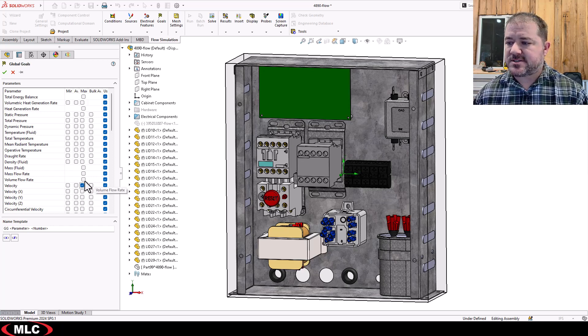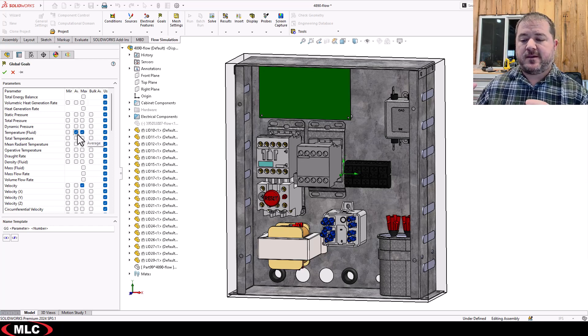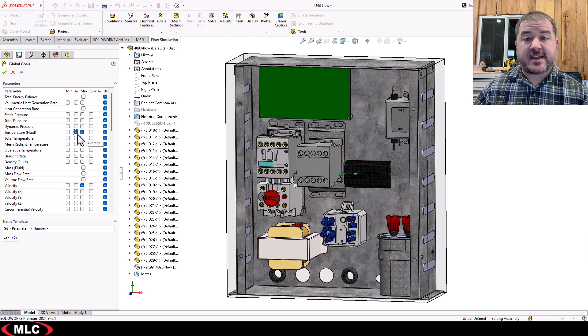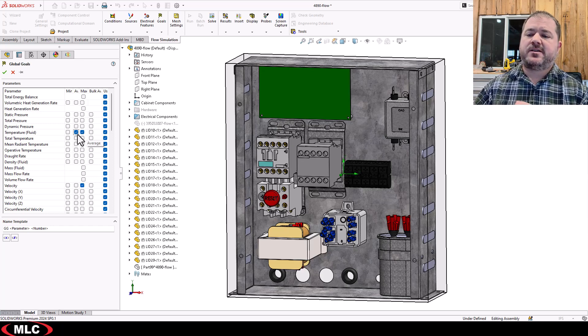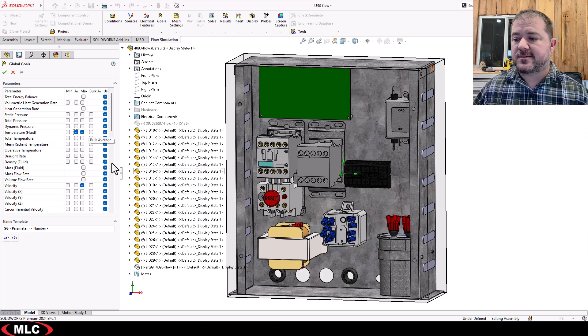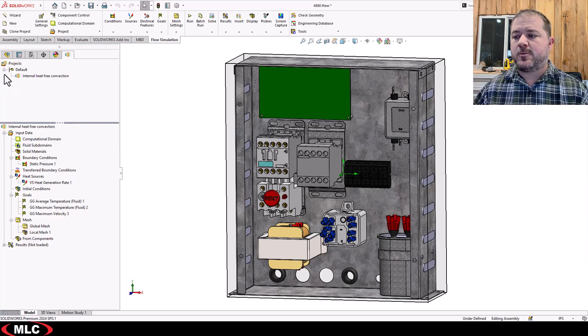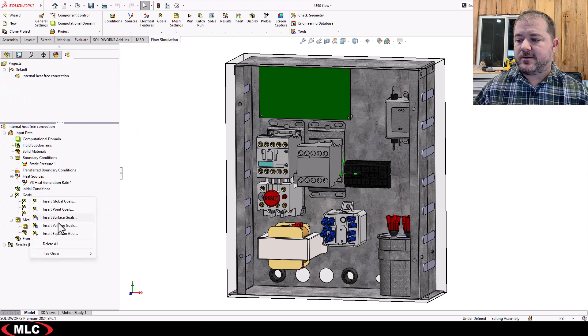I may also want to add another goal: the temperature of the fluid — maximum and average temperature of the fluid. We want to make sure that even once the transformer temperature has been achieved, the maximum and average temperatures have stabilized so we're not dealing with any warm-up parameters. We're looking for a true steady state, which may not really be achieved until a whole bunch of other things are fully resolved.